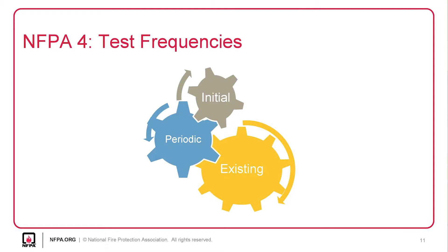So one of the things is for existing buildings: upon the adoption of NFPA 4, once a building code requires you to do integrated testing, you have up to 5 years to develop an integrated test plan for your building. It doesn't say you have to do the test plan, but within the test plan you develop, you have to establish a periodic time frame for doing your testing. Then that all has to be approved by the authority having jurisdiction.